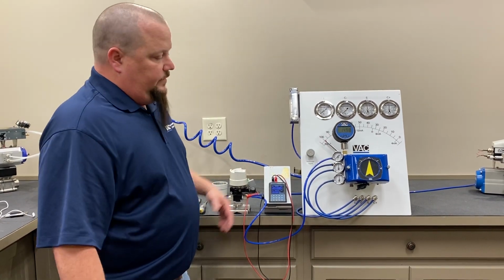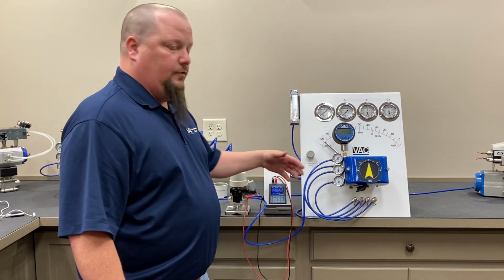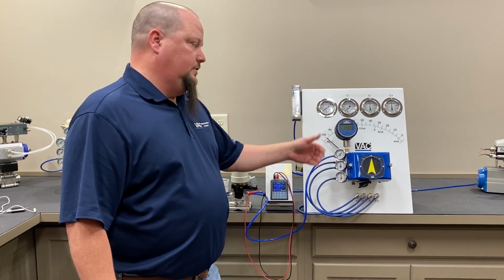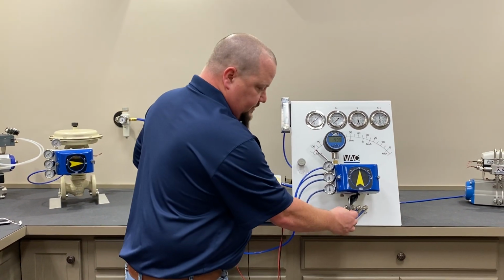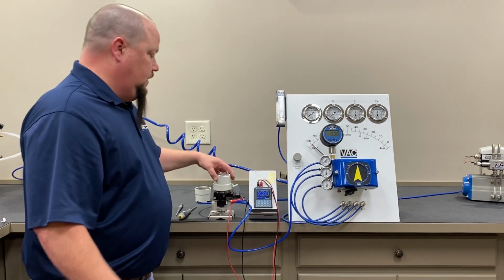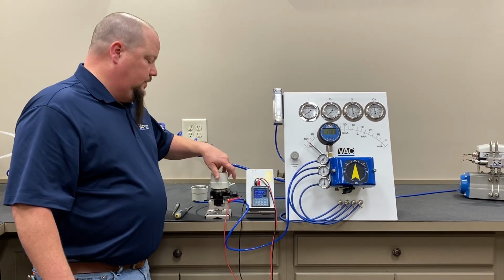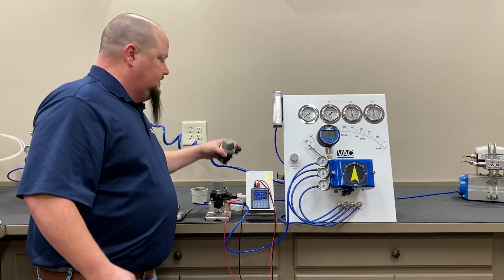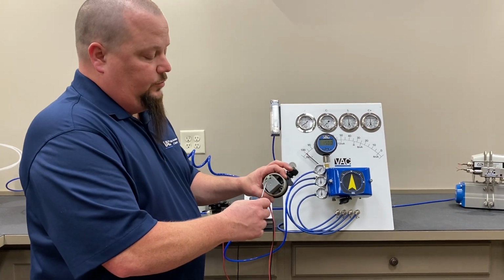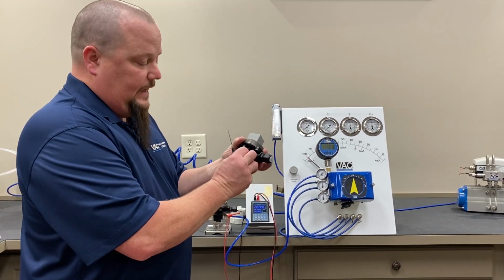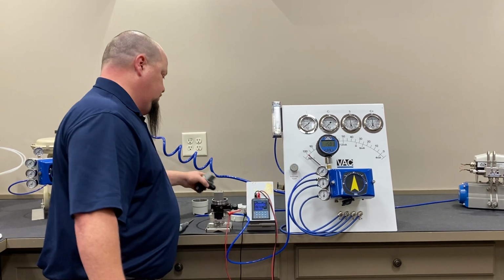You will then calibrate the unit as you normally do. At 4 and 20, 4 is your 0 and 20 is your span, and your calibration through the bottom port is as normal. You do not calibrate through the IDP. The IDP itself does have a 0 and a span calibration port, but that is to calibrate the IDP itself, not the positioner.